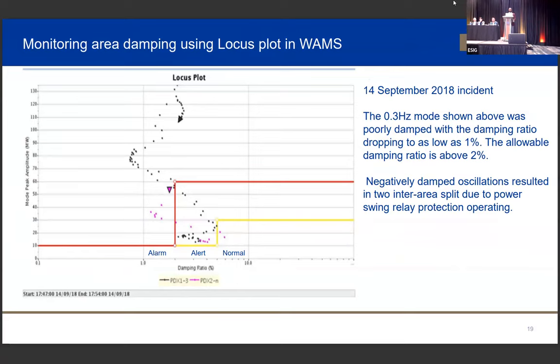Also from National Grid GB system operator. I just want to follow up on this question. So when you identify through the PMUs that some damping is negative, what action are you taking? Is that based on some offline studies, or is that based on real time, where you can actually determine which generator might be causing the oscillation? Yes, in real time we act because damping is low. Some of the controllers are in our neighboring countries, so what we do is call them to ask them if those controls are out.